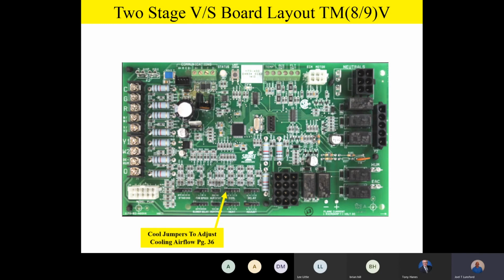If you've got a 2-stage unit outside, you've already set this up for 100% cooling airflow, but the board is smart enough that if it sees a Y1 cooling call in a 2-stage product, it will automatically reduce that cooling airflow to 65%. So again, just one of the nice things about the variable speed board: once you set your airflow up, the board makes some pretty intelligent decisions on the input that it gets from the thermostat. So it's a good board. It's easy to set up, but remember, your cool and adjust work together for your cooling airflow, and it's the 100% airflow you're actually setting up, and then the board will make a decision on cutting it back to 65% if you have a Y1 only call. Questions or comments on that so far? Is everybody good?